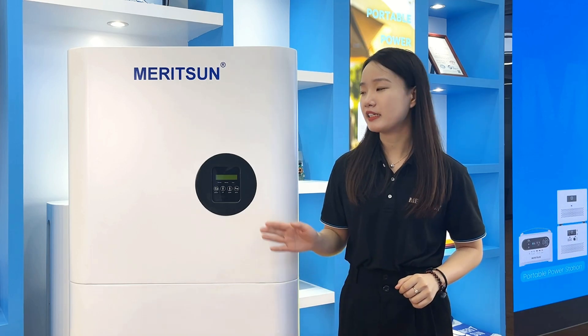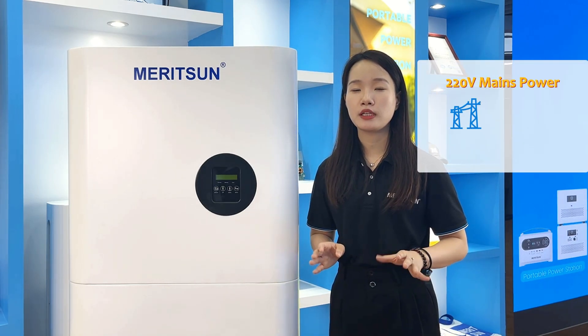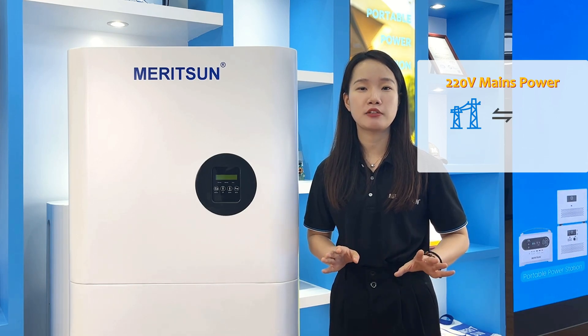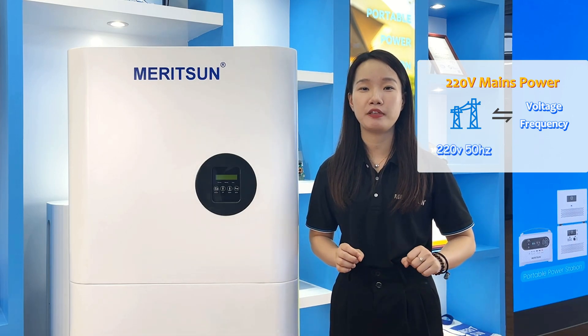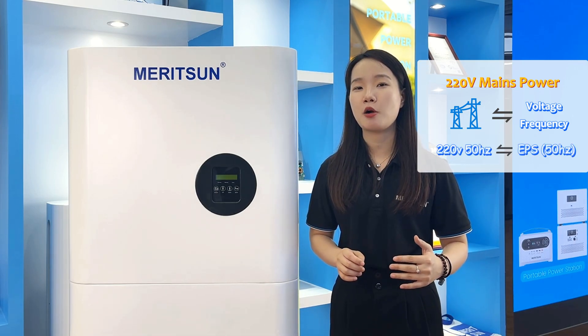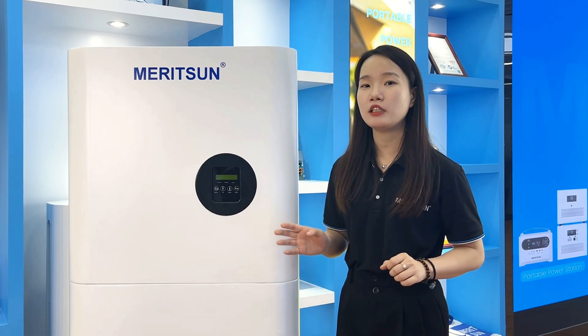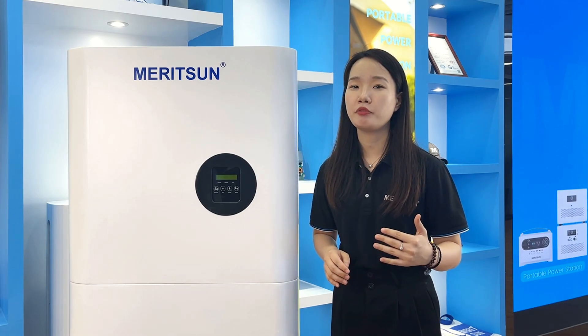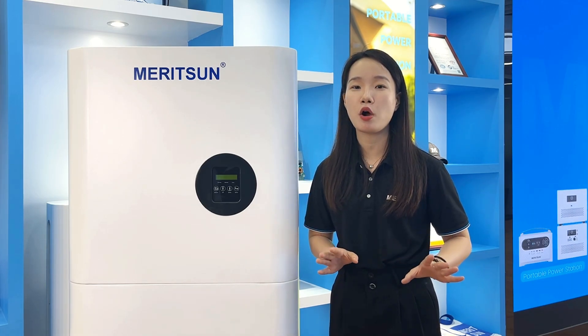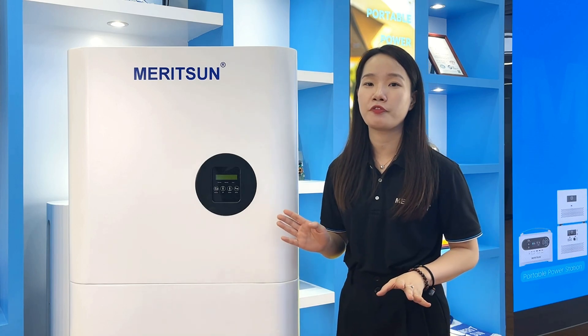The current version is the standard 220V model. If there is grid input, it will automatically adapt to the grid voltage and frequency. For example, if the grid power is 220V at 50Hz, the EPS output will naturally be controlled to 50Hz. However, if the grid was initially identified as 50Hz and then changes to 60Hz, the inverter will report a frequency out-of-range error. If it confirms 60Hz, the inverter will re-identify the grid frequency.